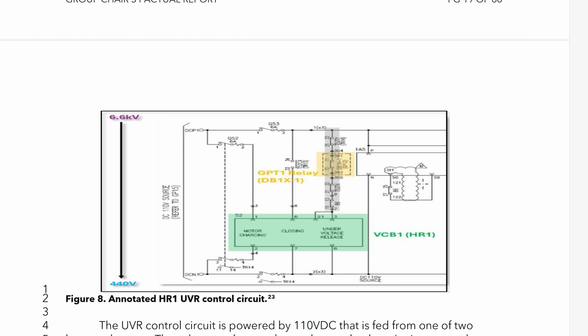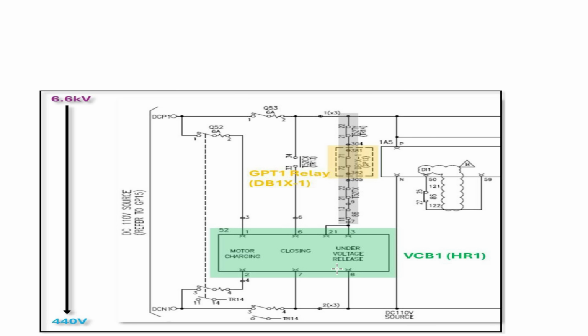Here's what they found. When they pulled HR1 out of the rack, they found this under voltage release control circuit. If it detects there's no voltage coming into it, this circuit will trigger the under voltage release, which will trigger HR1. That's what this whole circuit is, and you can see it's powered by 110 volts DC, with one rail and the other rail.